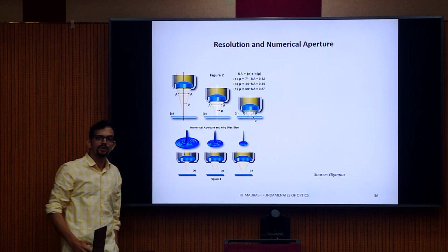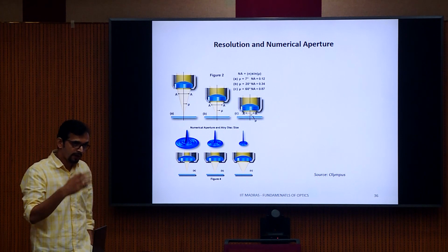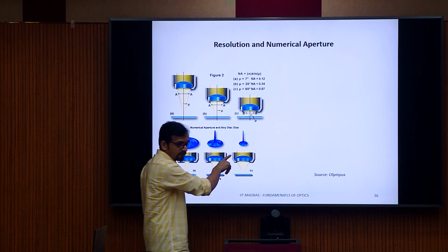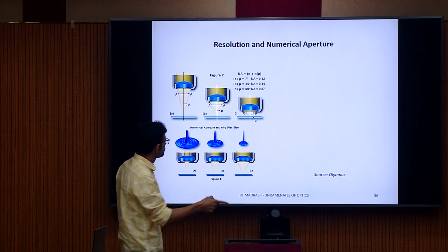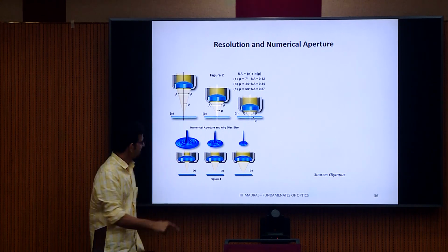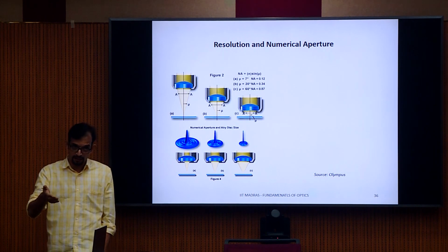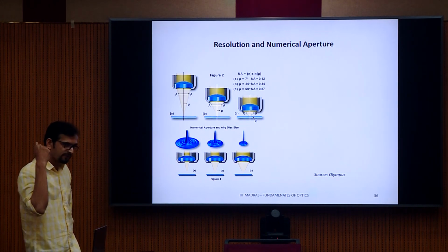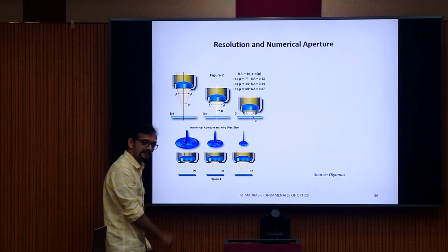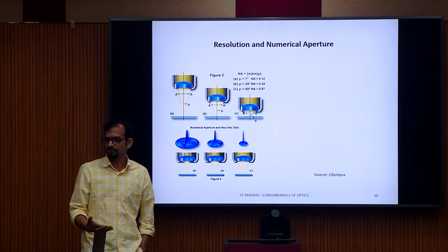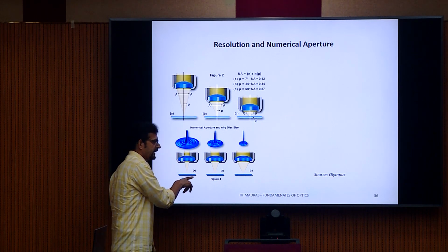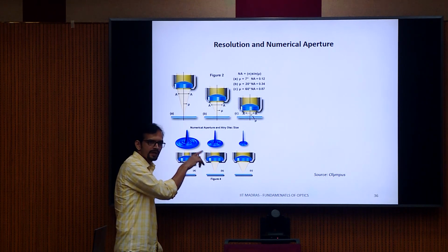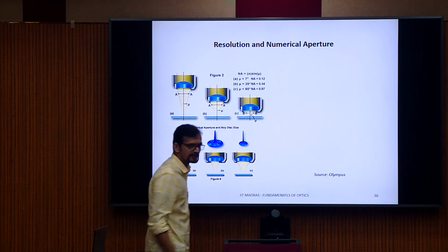This is also very important when we work with an optic system. We should know what is actually the back aperture of the final lens, and the magnification of the beam, we should define to fill that. Otherwise, even though you have a lens having a numerical aperture of 1.4, if your beam size is less, you are not going to utilize that completely. So these are the practical factors we have to really take into account when we design or when we work with that, okay?